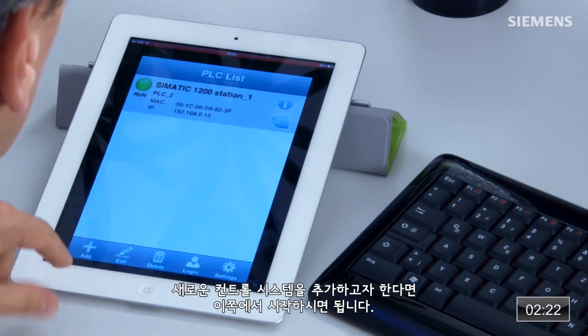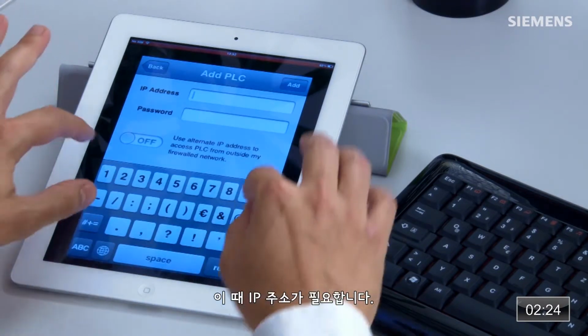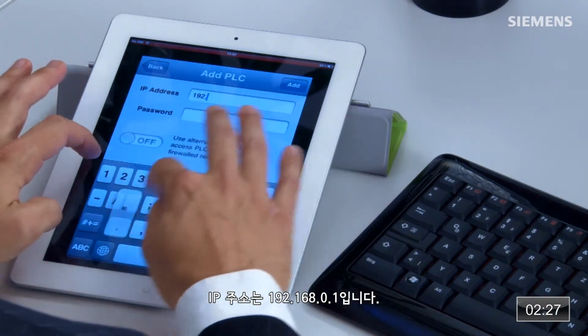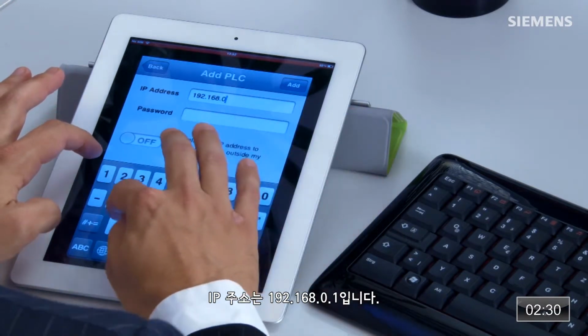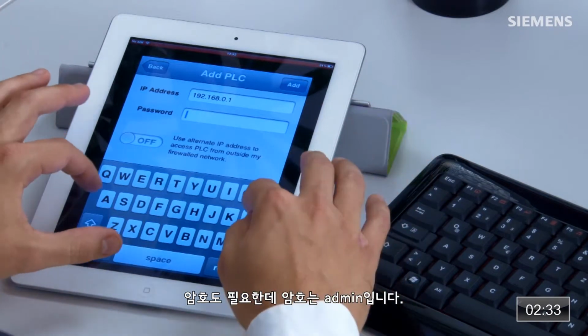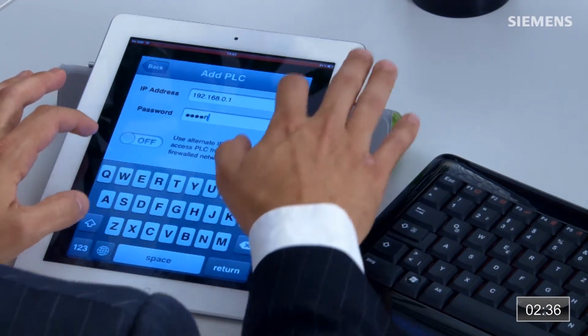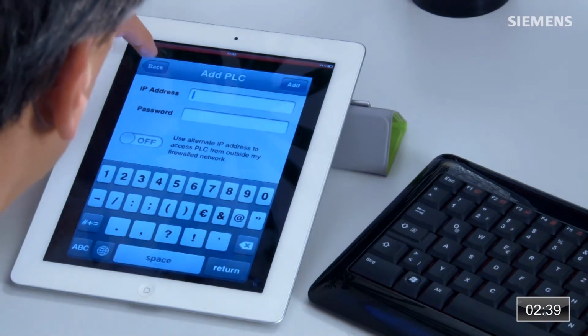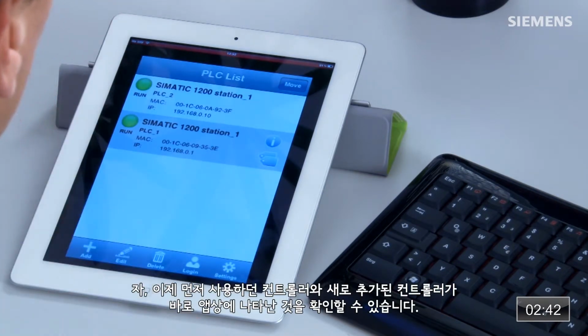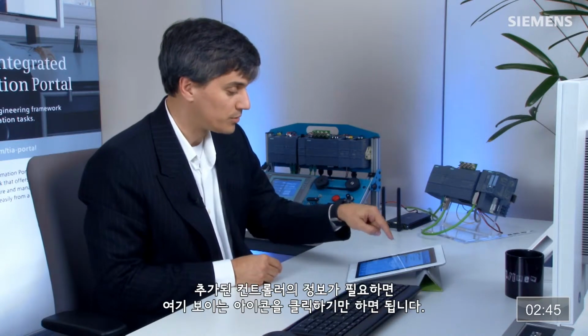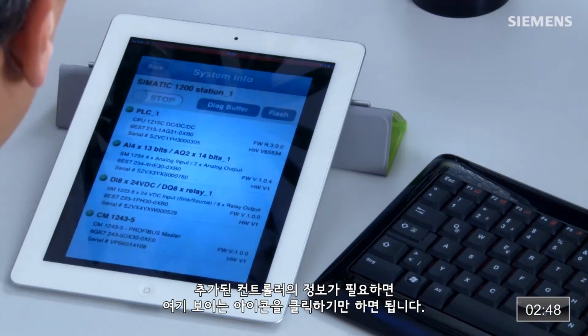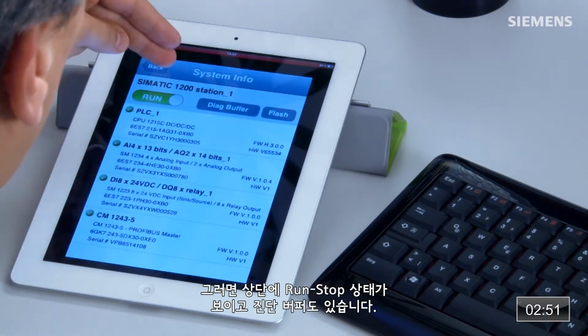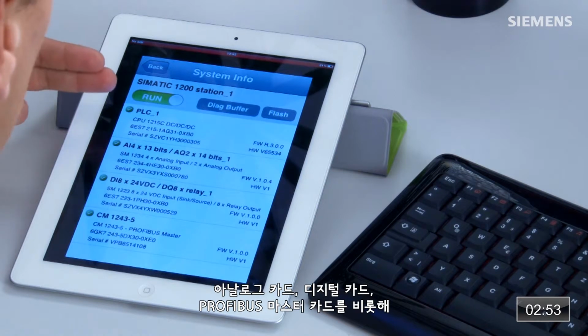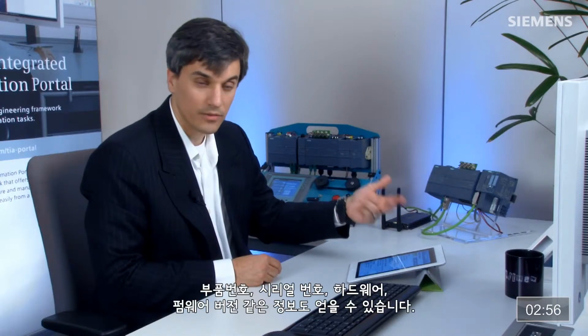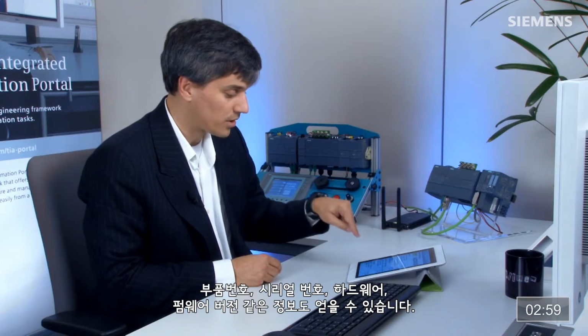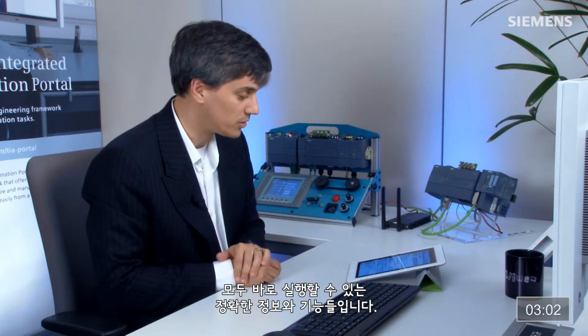And if I want to add the new control system, let's just start with this one. Go to add. It's going to require the IP address of 192.168.0.1, including the password. That's admin. Click add. And now it's added the controller. So now you can see we have the old controller and the new controller in this particular app right now. If I want to interrogate the new controller, just click on this icon right here. Now you can see across the top we have the run stop state and a diagnostic buffer. We also have the controller with all the part numbers, serial numbers, hardware, firmware versions, including an analog card, digital card, and a Profibus master card, and that is all correct and everything's good to go right now.